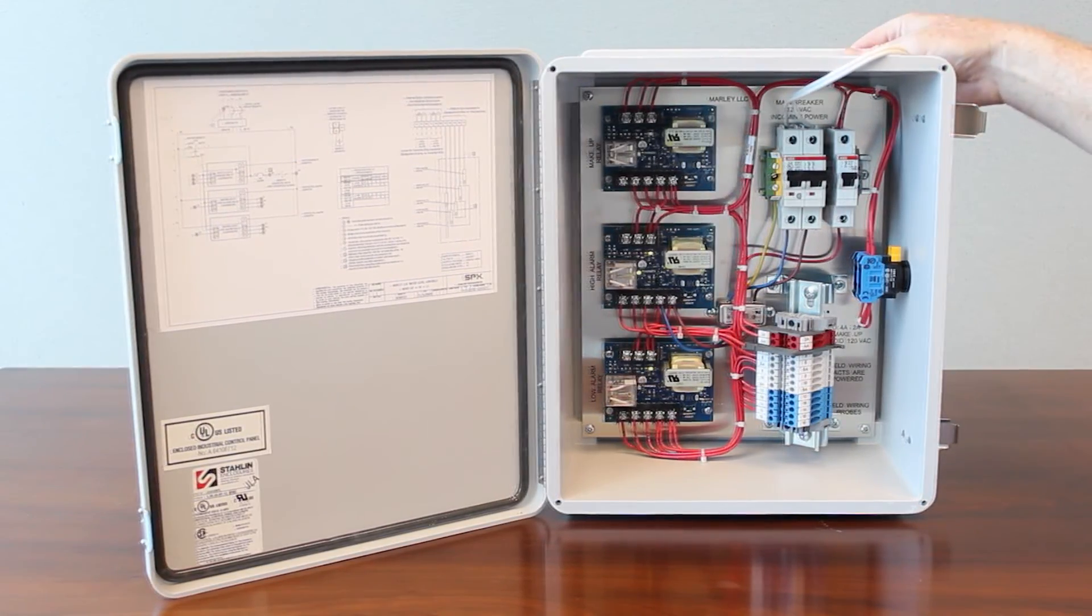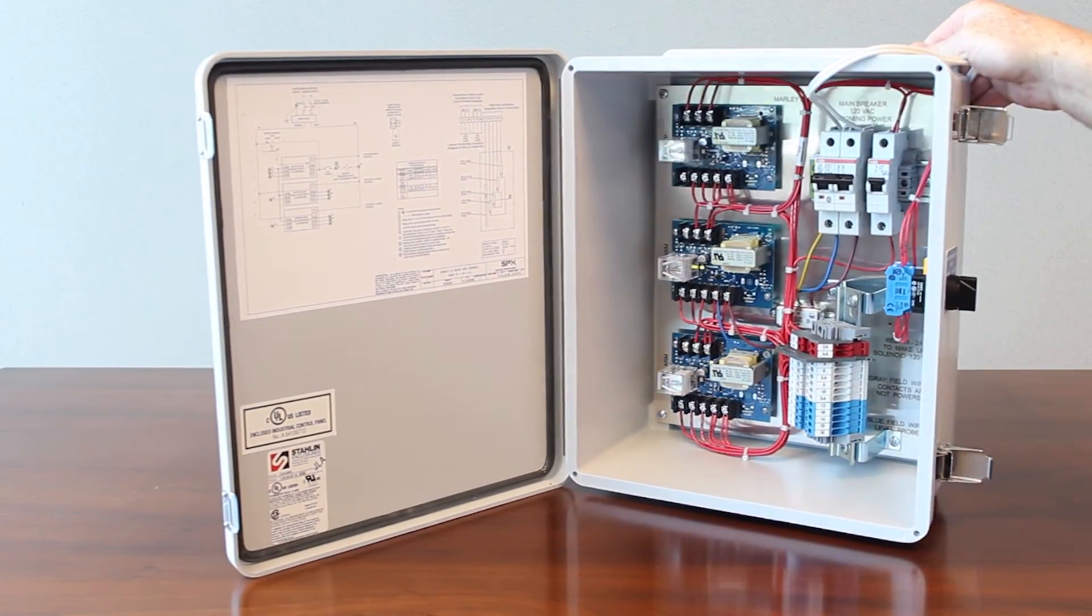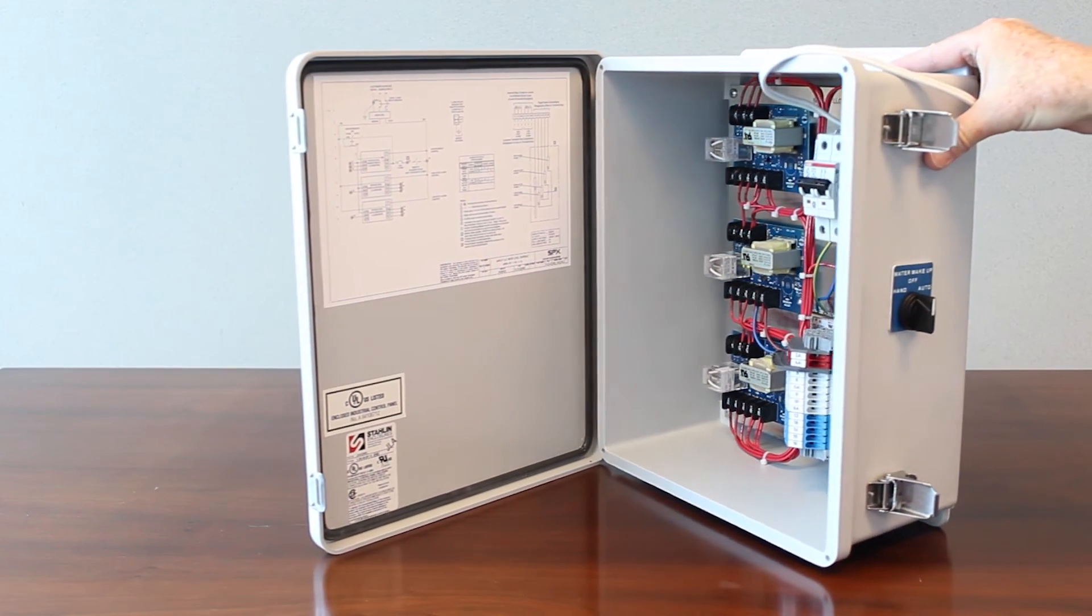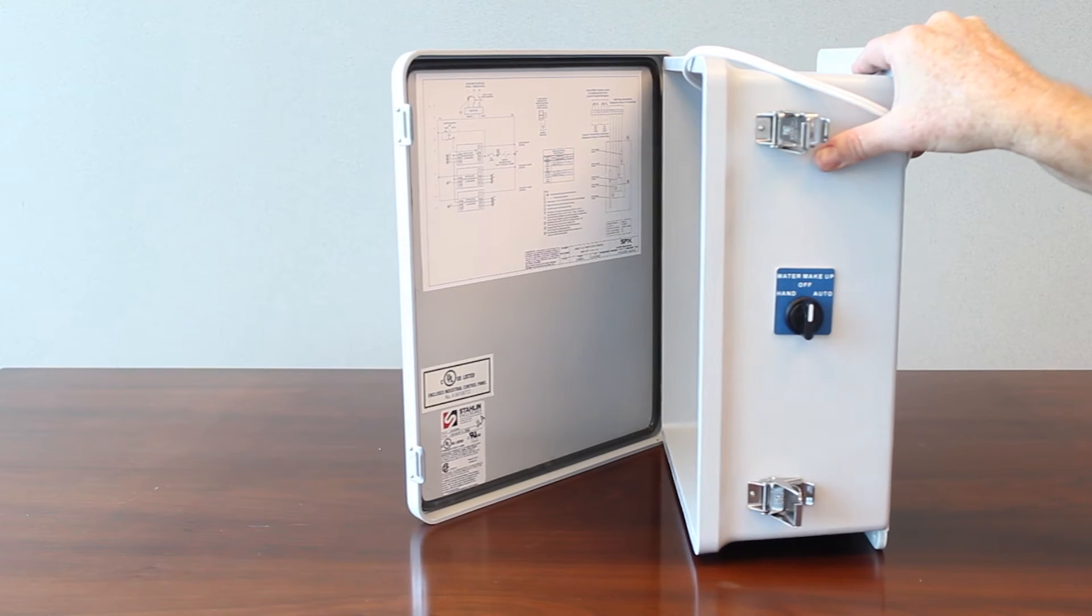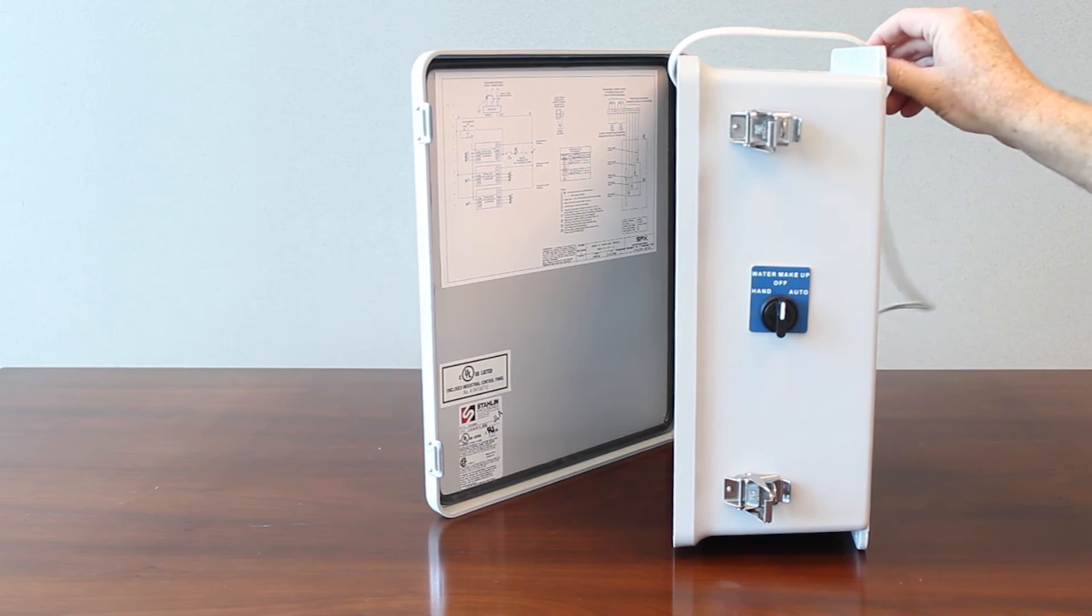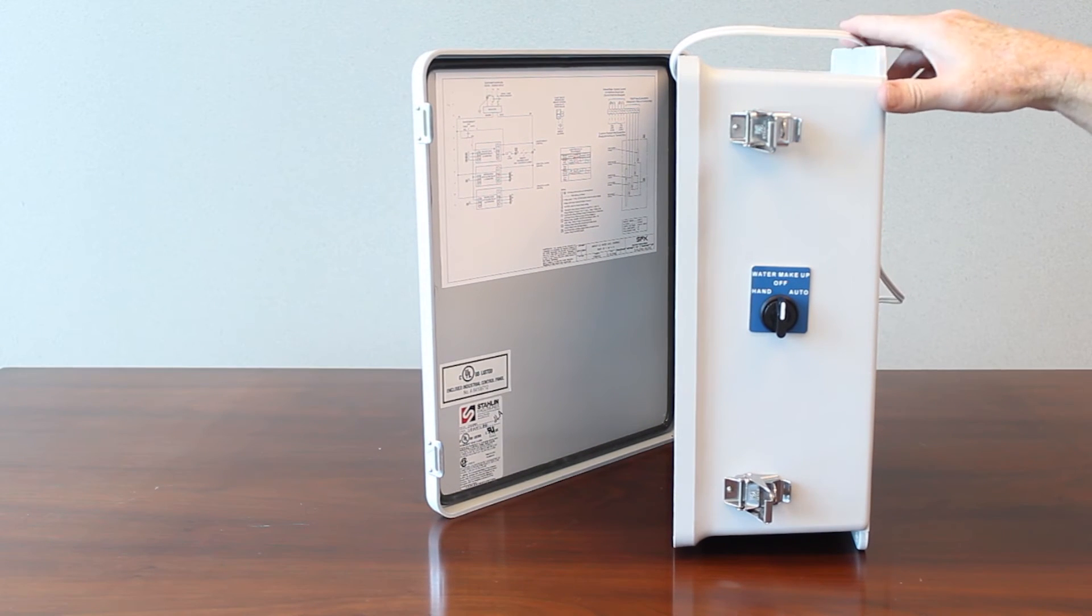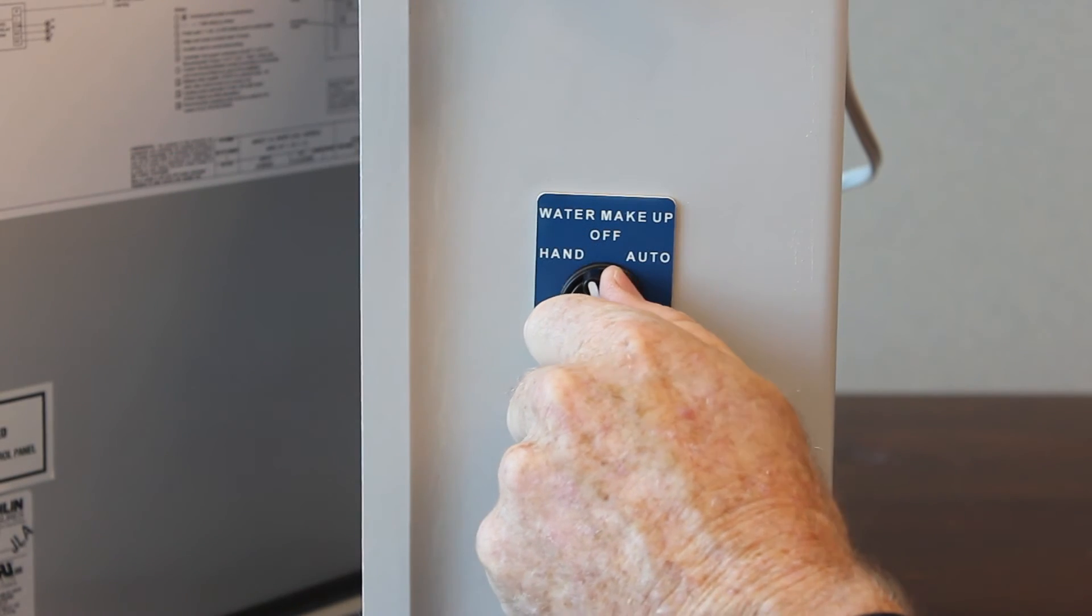When you're first doing the startup on a cooling tower typically there's no water in the basin. So if you have your solenoid installed into the water makeup piping and wired to this panel to add water into a dry basin, you can simply rotate this to the hand position.